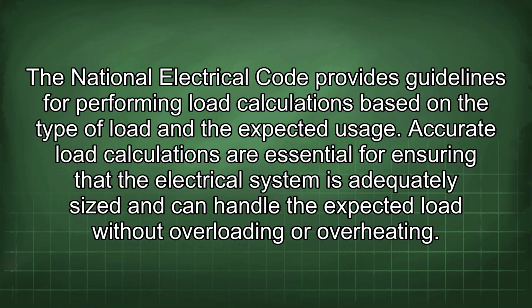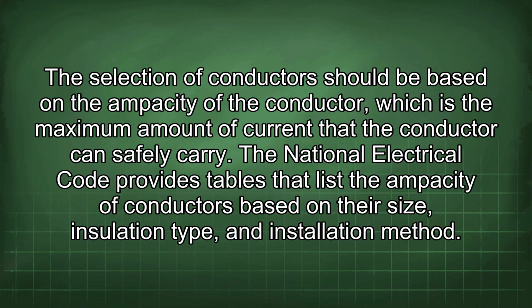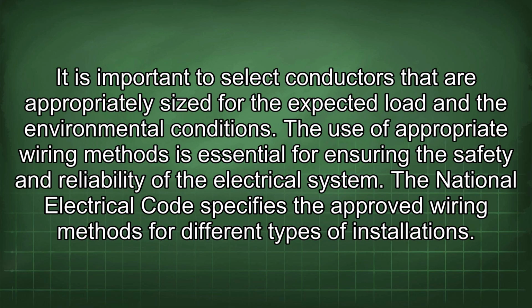The selection of conductor should be based on the ampacity of the conductor, which is the maximum amount of current that the conductor can safely carry. The National Electrical Code provides tables that list the ampacity of conductors based on their size, insulation type, and installation method. It is important to select conductors that are appropriately sized for the expected load and the environmental conditions.